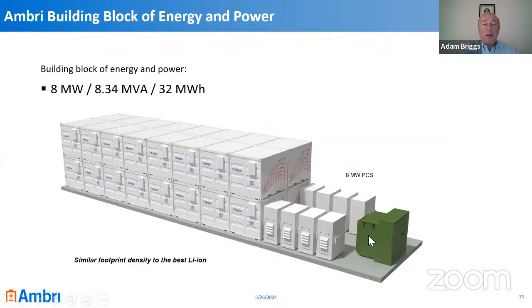When we bid on projects, we typically bid in this type of structure. This happens to be a 4-hour discharge system, so 32 megawatt hours with a power capability of 8 megawatts, meaning 4 hours of operating time. We marry, in this case, 32 one-megawatt-hour containers with 8 megawatts of inverters and a 9 MVA, or 9 megawatt, transformer. That could be a standalone project.